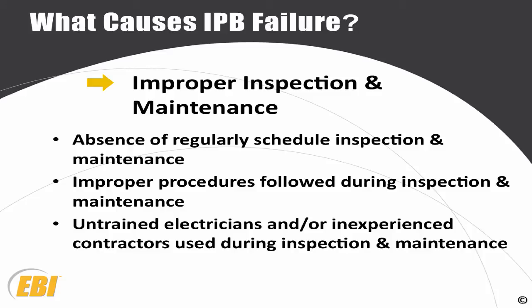The major problem we run into is improper inspection and maintenance. A lot of plants do not have an adequate schedule for the inspection and maintenance. A lot of times they don't use the proper procedures during the inspection and maintenance. And then also they have untrained electricians or inexperienced contractors that will do the inspection and maintenance. You can have a good journeyman electrician, but if he does not work on isolated phase bus continuously, he would not know a problem if he was holding it in his hand looking at it.